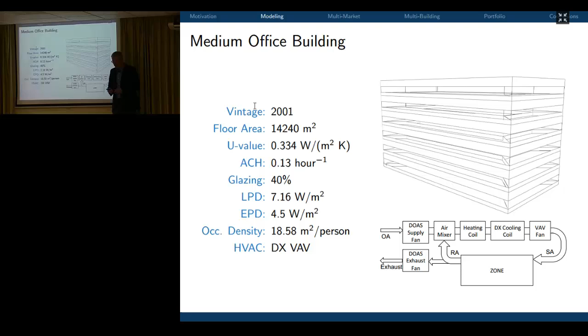And it's using a variable air volume system. I mentioned to you, it's a system that changes the amount of air. And we use a direct expansion cooling system, where refrigerant is expanded directly in the coil, then compressed, then condensed. And this picture looks almost similar. Here we have, however, a special system that is a dedicated outdoor air system, but we have a DX cooling, we have a variable air volume fan, and we serve the entire building.